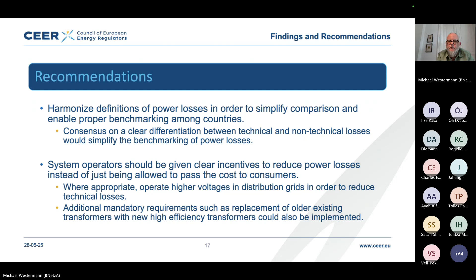We find that system operators should be given clear incentives to reduce power losses instead of just being allowed to pass through the cost. That could mean operating on higher voltage levels, for example, or replacing older transformers with new high efficiency transformers.